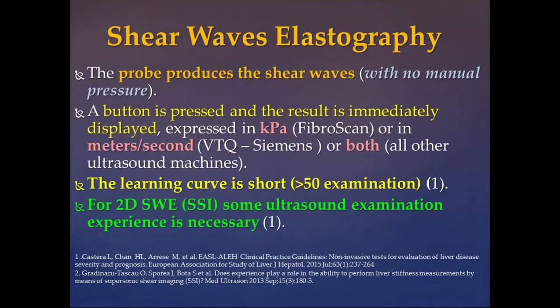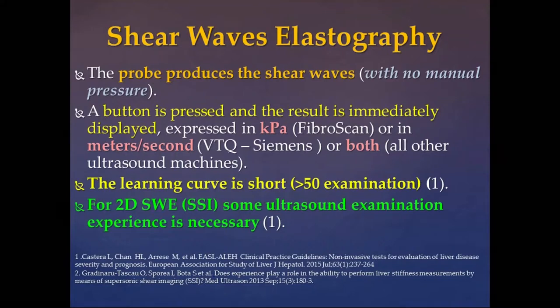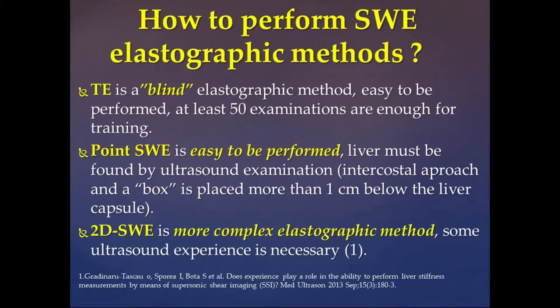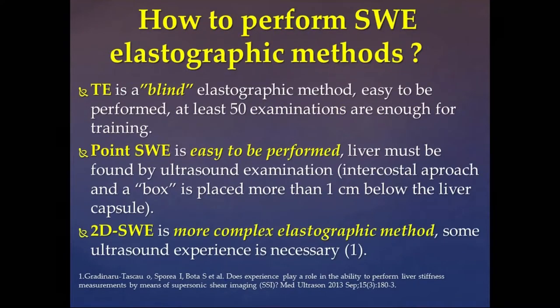Shear wave elastography is very simple. The probe produces shear waves — we don't need to apply any pressure. Usually we find the liver, put a box, push a button, and have the results very quickly, expressed in kilopascal or meters per second, or both on most machines. The learning curve is very short — usually 50 examinations is enough to gain some experience, though for 2D SWE some additional ultrasound experience is necessary.